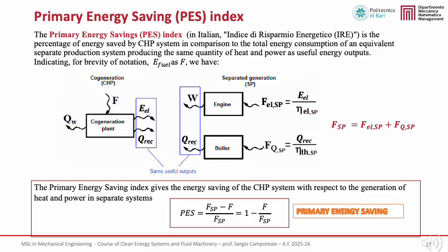If we denote by F the fuel input to the cogeneration plant, and by F sub SP the total primary energy input required by the separated reference system, the PES index is defined as the ratio of the primary energy saved to the primary energy consumption of separate production. A positive value of the PES index means that cogeneration requires less primary energy than separate production.